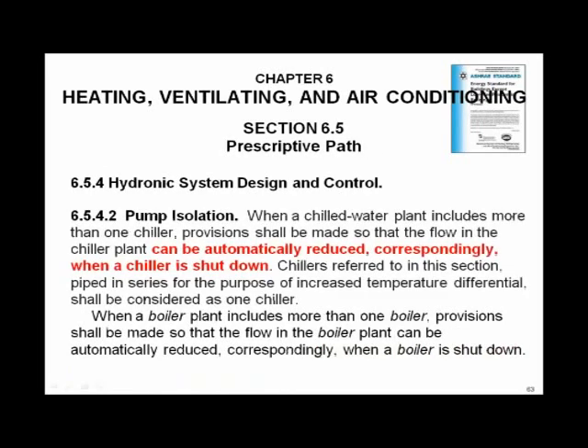Pump isolation, pretty straightforward, but on a chiller and a boiler, if a chiller is not running, a boiler is not running, condenser is not running, you have to valve it off. You don't want water flow through a heat exchanger that's not doing any work.